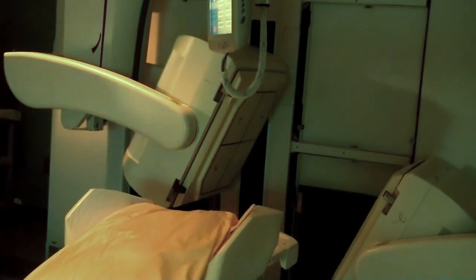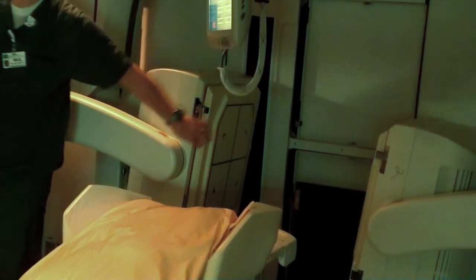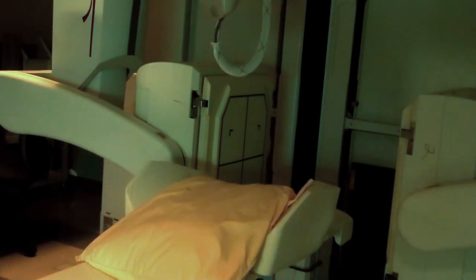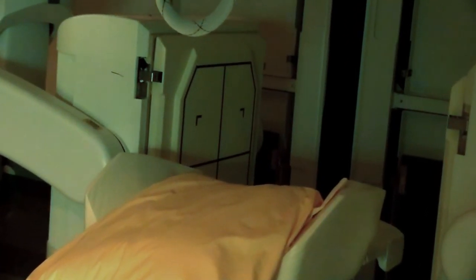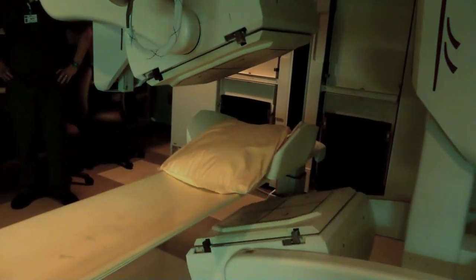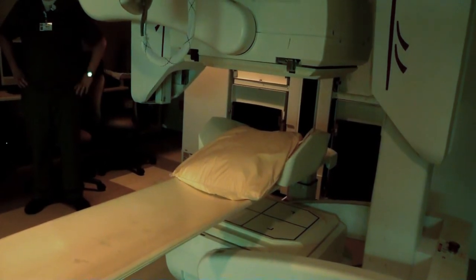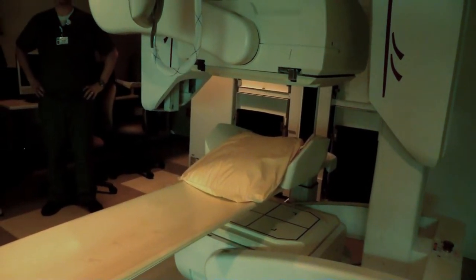On the camera here, these lead plates are about two inches thick. They have little cuts in them that basically stop those gamma rays that are going the wrong direction, and they keep it so the image can look really well. Those are called collimators. You can see back here there's the tape — we have those that we can change out for different types of radioactivity. They're very, very heavy. Each one of those weighs about 300 pounds. That's why it's all automated on the table system so we don't have to lift them ourselves.